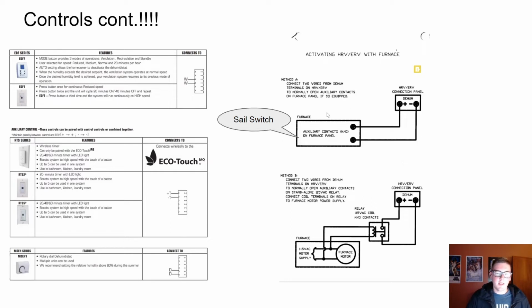And what I did was put one of those in my ductwork such that when the furnace blower came on, whether it be for recirc, for cooling, or for heating, that contact closes and the ERV also turns on, and then I have full control and am always ensured that both devices are on at the same time when I want them on, and not just one or just the other. So that worked out really well.